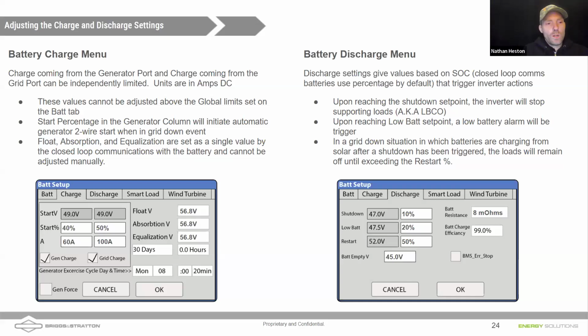So what the settings that you see there, the start setting is, hey, if my battery percentage drops below 40% and there's no utility source, there's no grid source, automatically start up the generator. So it'll send a 2-wire signal to start a generator if you have one, right? And then it will limit the amount of charging that it does from that generator port to 60 amps DC, right?